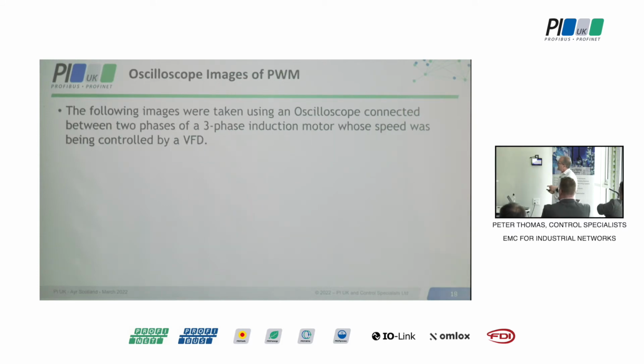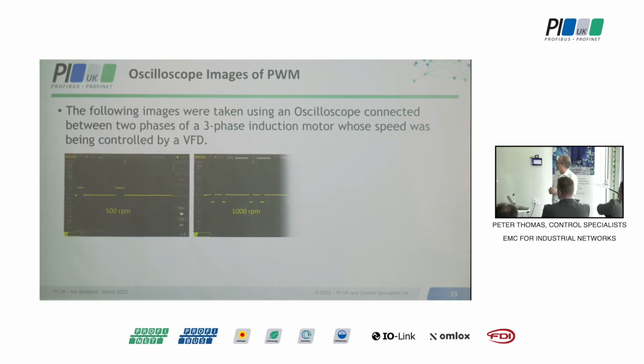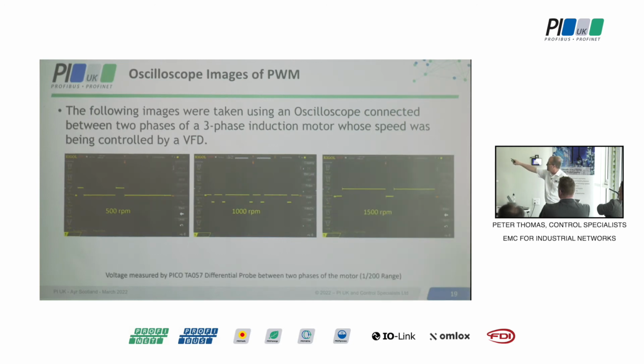Now, here's the slides that I wanted to show you, taken using an oscilloscope connected between two phases of an induction motor whose speed was being controlled by a variable frequency drive. These look small, but I had quite a large scale on there, and you can see them - these are the pulses. On this one, a 1-200 range, so basically they are 600 volts. And you can see as we increase the speed, it's on more times than it's off. So that's all we see.